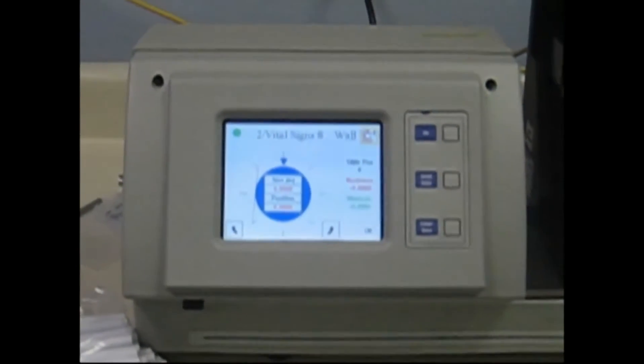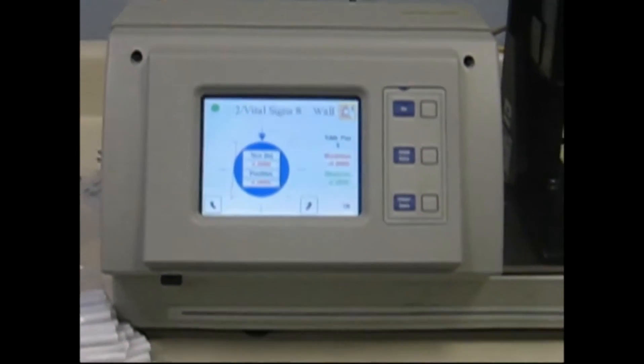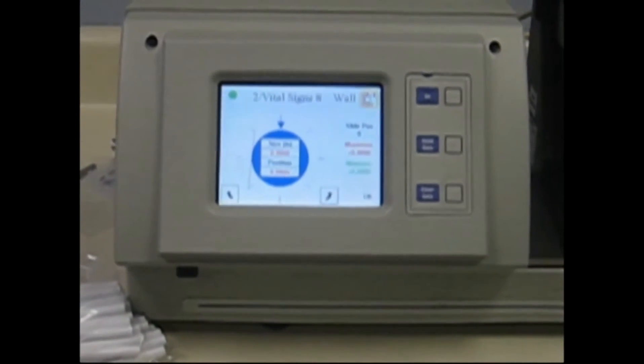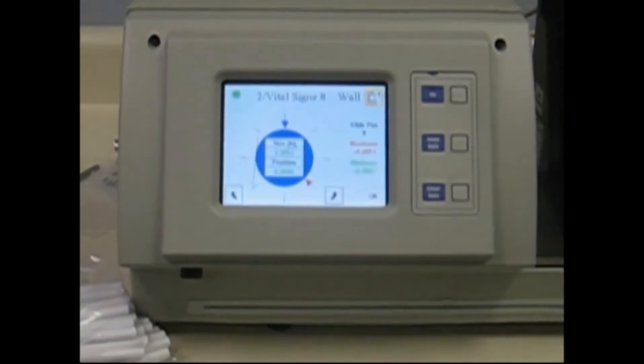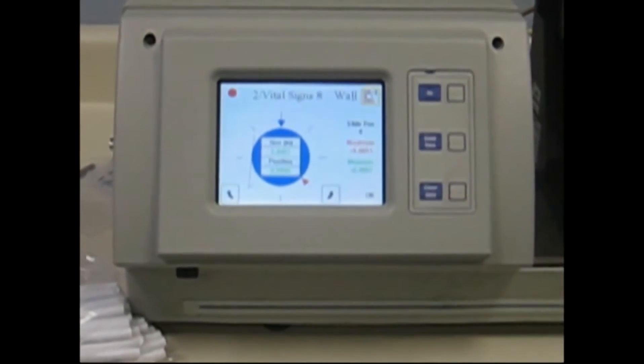What will happen now, if everything's set up properly, is that the fixture will rotate the tube sample around the mandrel and take a reading. When it's done, the little icon in the corner will go from green to red, and the numbers will appear on the screen.